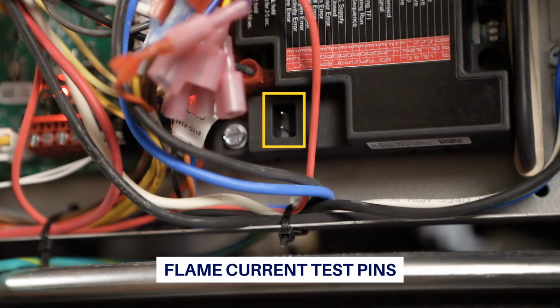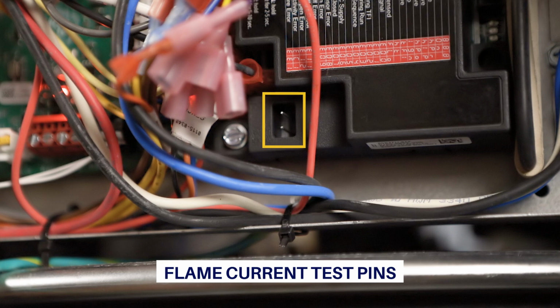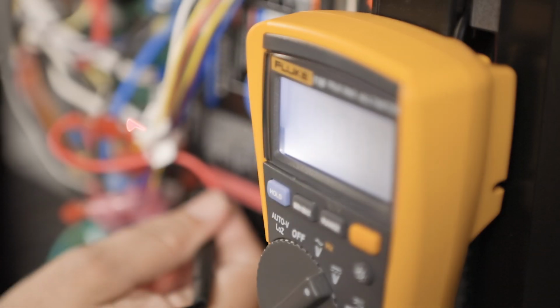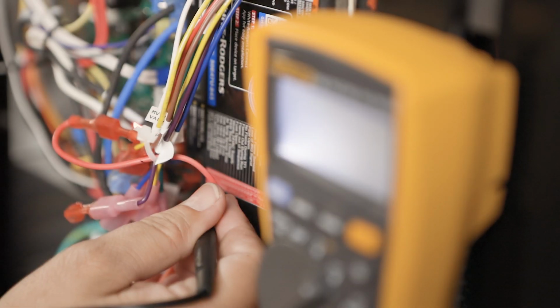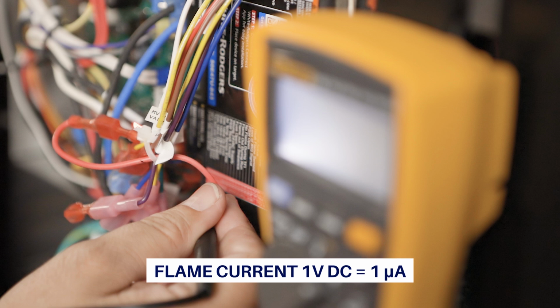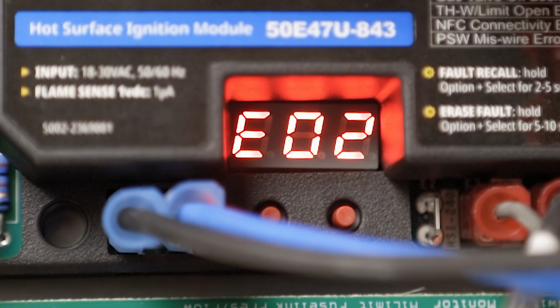The 50E47U-843 also comes with flame current test pins. These pins are easy to access and provide the flame current reading. If it's preferred to test the flame current using your own meter, set a voltmeter to DC volts and measure across the pins while a flame is present on the sensor probe. 1 volt DC equals 1 microamp. The onboard display conveys the system status and active fault codes.